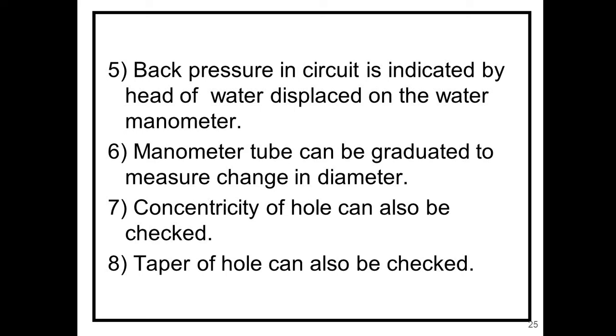There are some disadvantages also. It requires auxiliary equipment like a pressure regulator, so that is one thing. When using a glass tube as the indicating device, it is necessary to use high magnification to avoid errors of reading. We are familiar with taking the reading using a manometer. Everybody faces difficulty taking the reading using the manometer, isn't it? So a magnification device is required to avoid the error of reading.